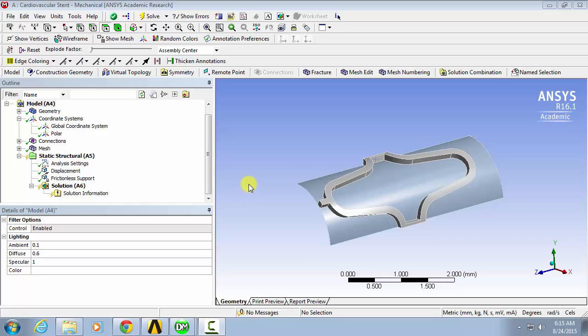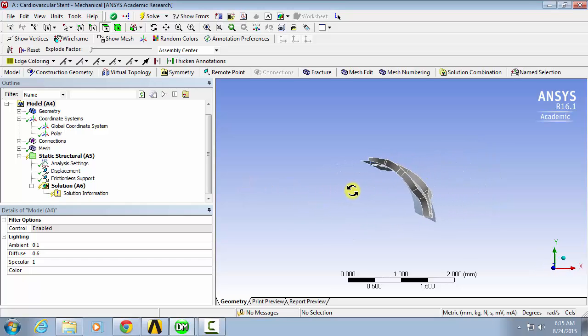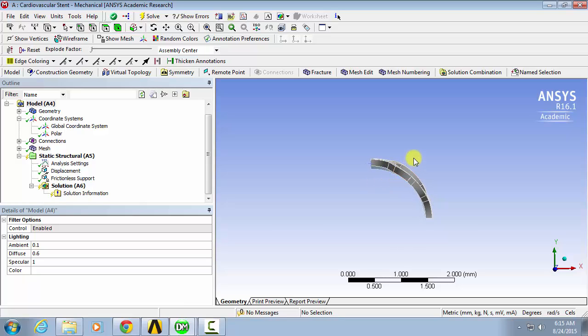Because of pretty strict FDA submission guidelines for stents, we already have a few pieces of solution information we're looking to gather, such as recoil percentage, which is the percentage that the stent will deform back to its original shape after expansion.